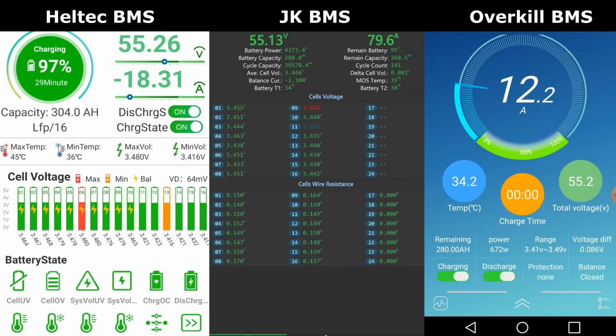On the left, we have the Heltec BMS in the top battery shelf, showing us 55.2 volts. We are still charging with around 19 to 20 amps. We know the shunt is not very calibrated in the Heltec BMS, so it always shows a bit less than it actually is. Deviation is 70 millivolts, and cell number 1 to 10 is still balancing, so nothing has changed there, at least.